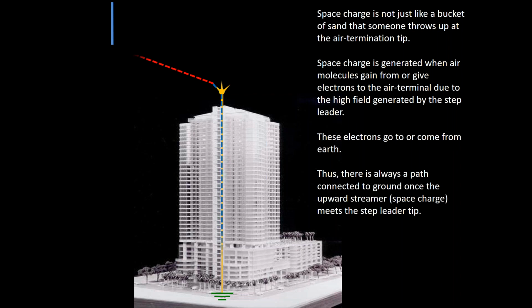However, what these vendors do is go to a testing facility, for example SAIEE, and ask for their rod to be tested for this maximum current testing. And the SAIEE does the testing because they have to do that. It is according to the IEC standard, and they say that SAIEE certifies that this rod can withstand 100 kiloampere current for mechanical and thermal stability. And then these people will show this certificate to the people and say, you see, even SAIEE under IEC 62305 has certified our product. This is done by each and every vendor that I have come across.